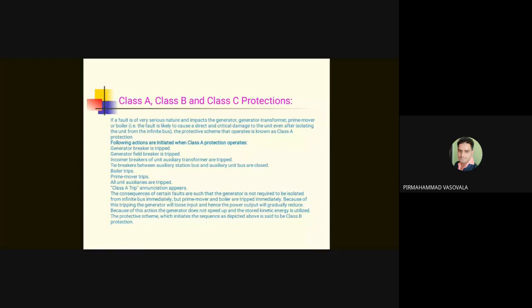You might also know, probably you would have studied, the different types of generation. You might have studied thermal power plants, in which the power plant requires 10% of the power that is generated for running its own auxiliaries. So that is fed through the unit auxiliary transformer. So if there is a fault in the unit auxiliary transformer, that also falls in the generator fault.